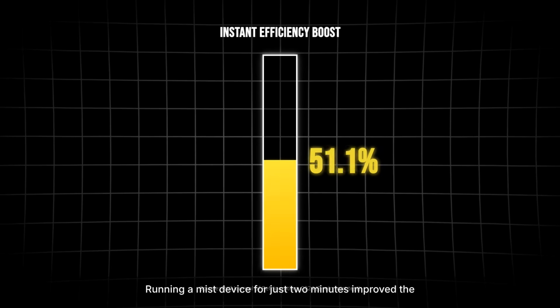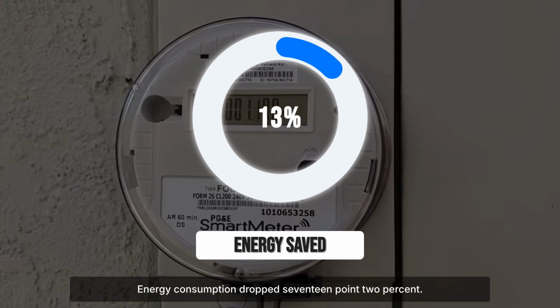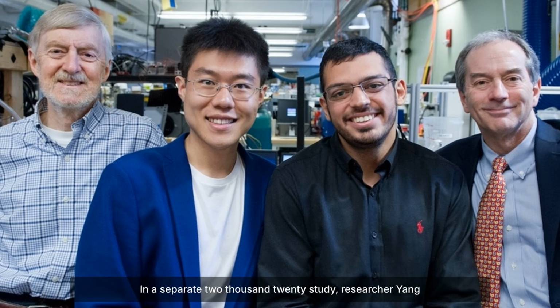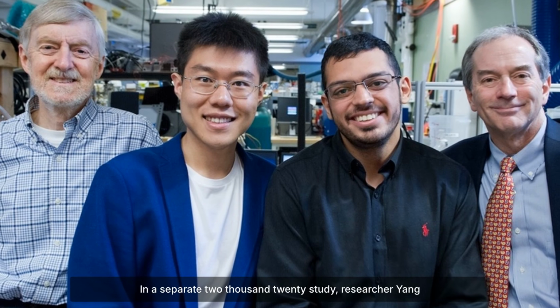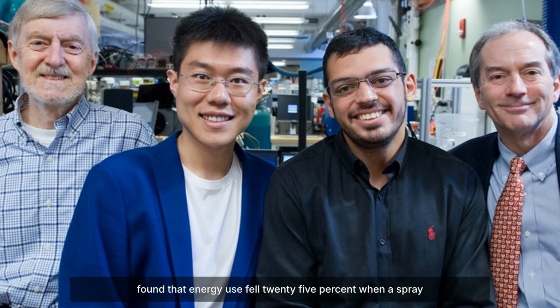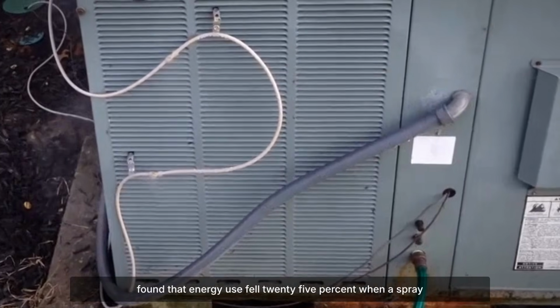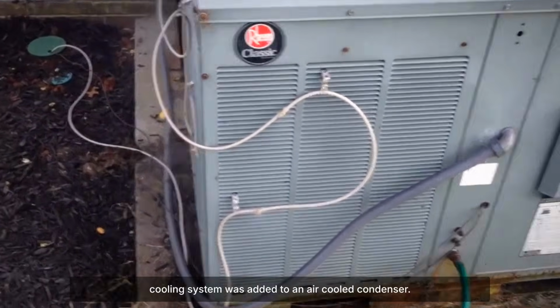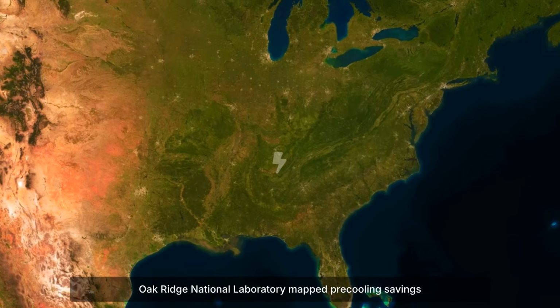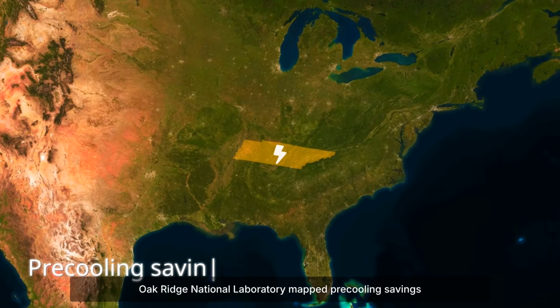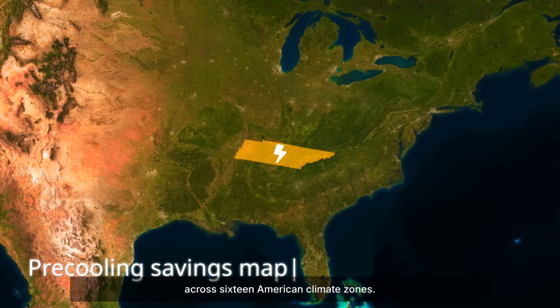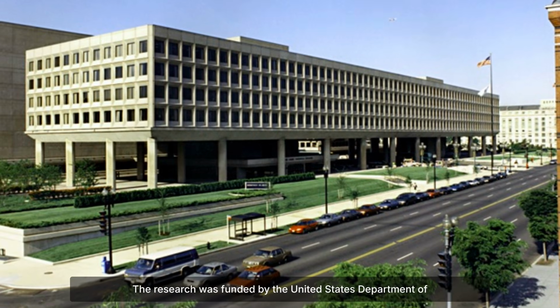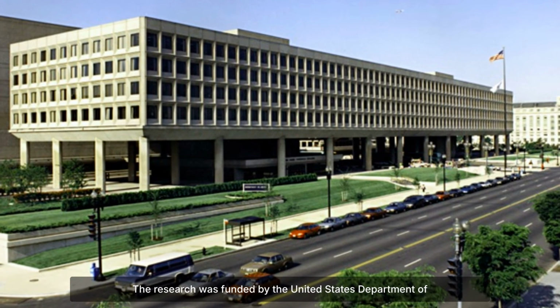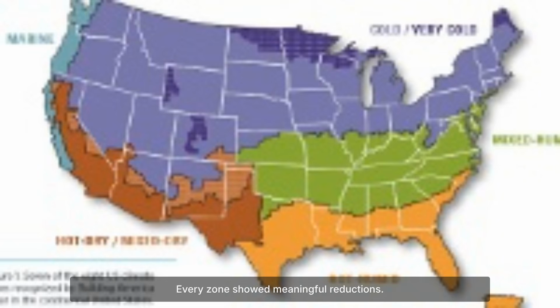Running a mist device for just 2 minutes improved the coefficient of performance by 54.9%. Energy consumption dropped 17.2%. In a separate 2020 study, researcher Yang found that energy use fell 25% when a spray cooling system was added to an air-cooled condenser. Oak Ridge National Laboratory mapped pre-cooling savings across 16 American climate zones. The research was funded by the United States Department of Energy. Every zone showed meaningful reductions.